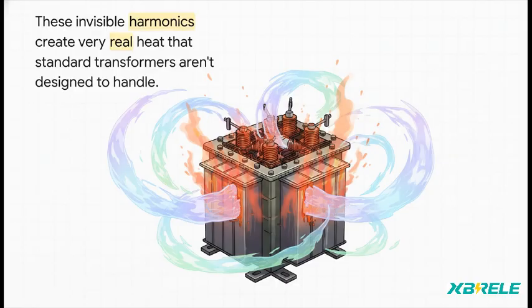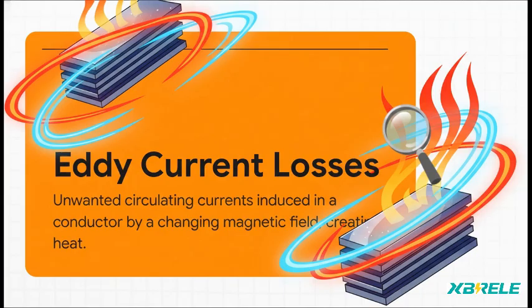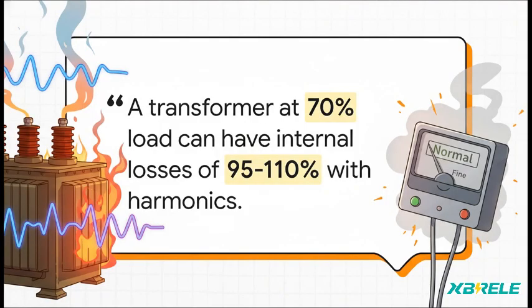And here's the kicker. All these invisible harmonics create very real extra heat. A big chunk of that heat comes from something called eddy current losses. And check this out. The higher the harmonic, the worse it gets. The 7th harmonic, 49 times the loss. So your meter says 70%, but the transformer is literally cooking itself from the inside.